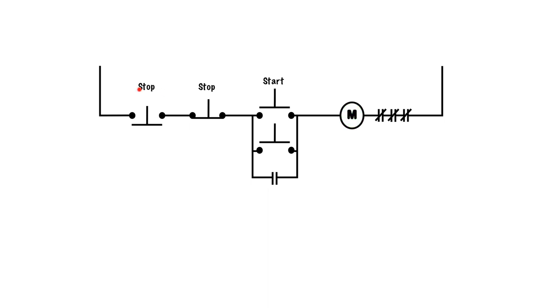Now to shut the circuit off, we push down on our normally closed contact, which will open up this circuit and de-energize M. When M de-energizes the coil, then the contacts will open up. When we let go of the stop button, everything will be de-energized because this is open, this is open, and this is open. These are all back into their normally closed positions. The starts are in their normally open positions, and our set of contacts is normally open because M coil is not energized.